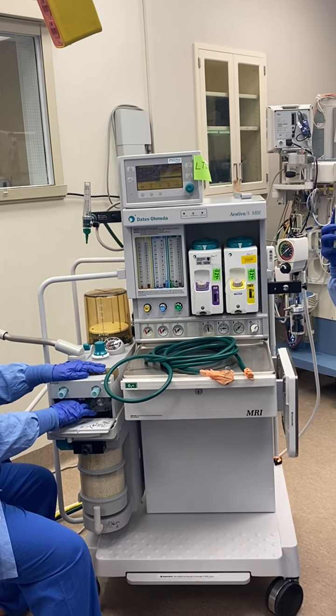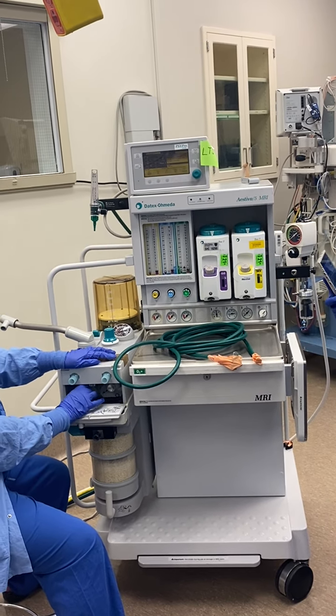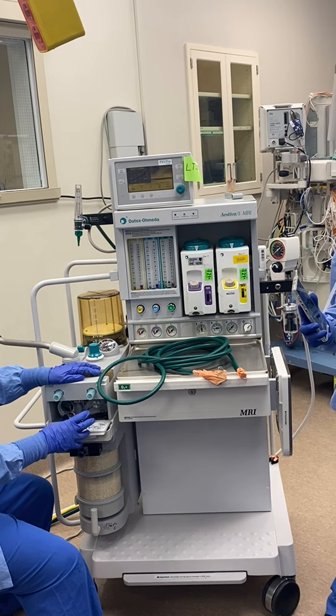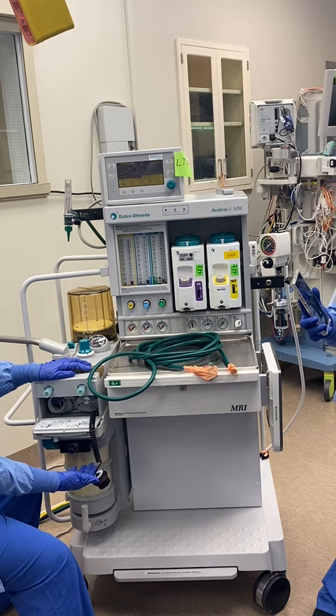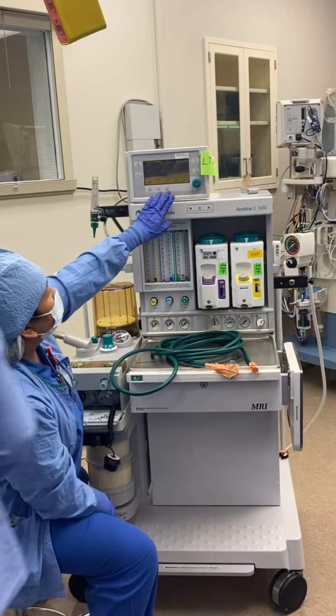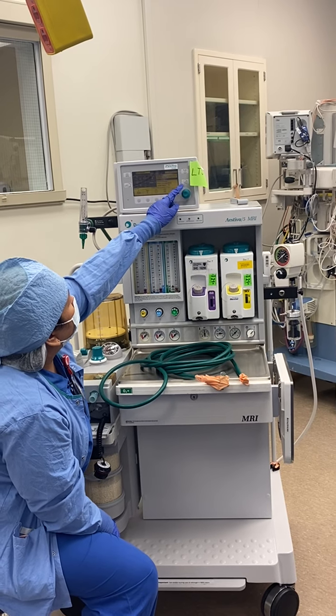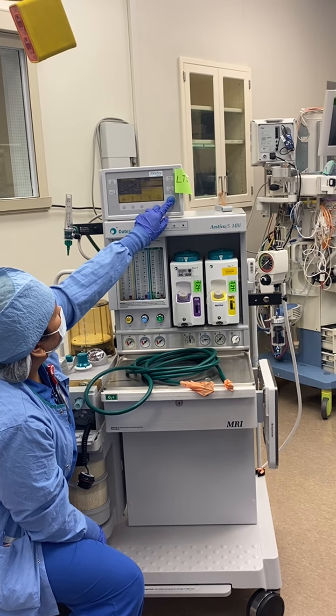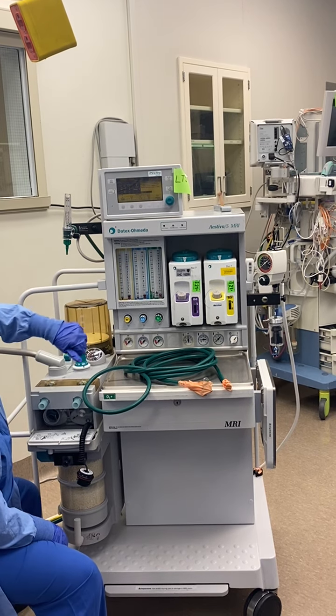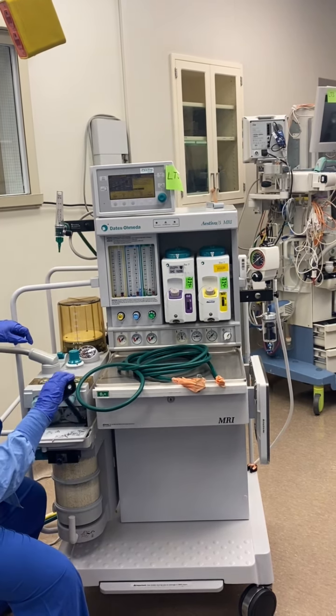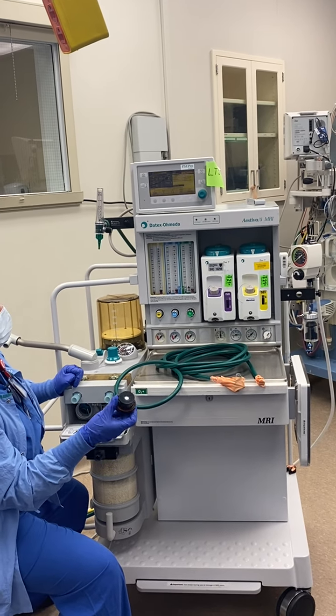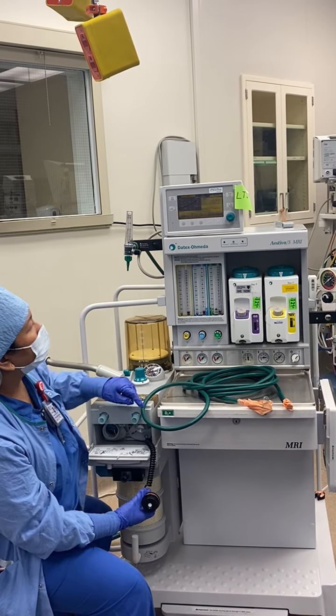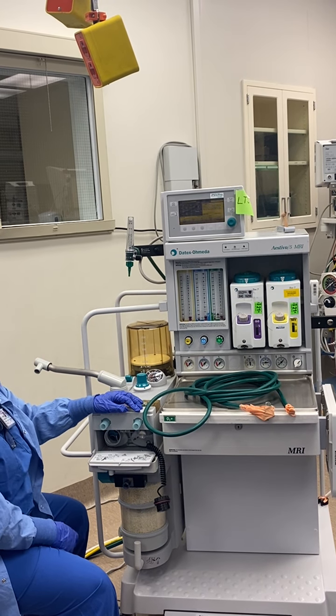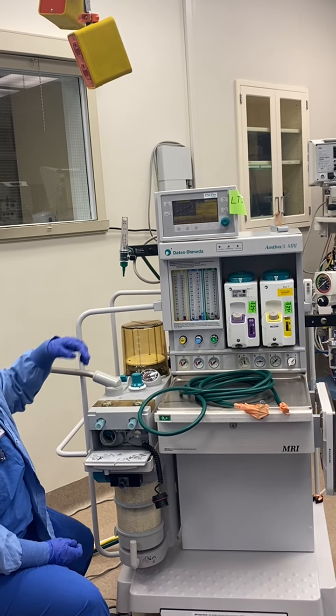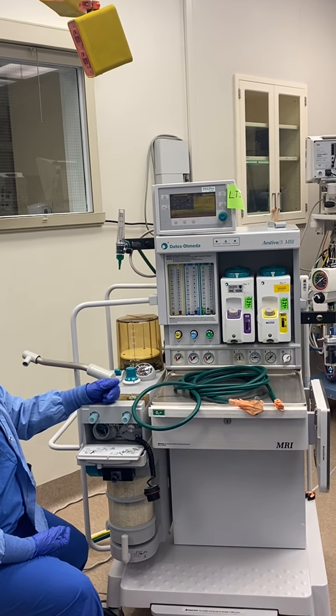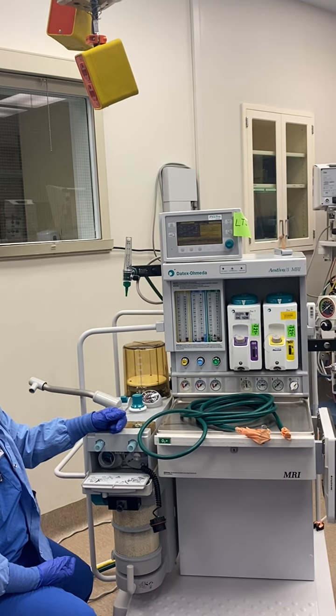Is it the same as the flow sensor? Yes. You're going to leave this flow sensor in open air, just like that. Okay? And then it says remove O2 sensor from the breathing circuit, expose it to room air, and push the knob. Oh, this one you don't have to do for 2 minutes? I don't know how many minutes it takes. I mean, we get to see how long it takes. They're all different.